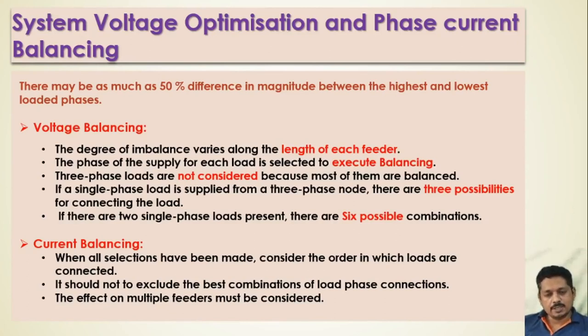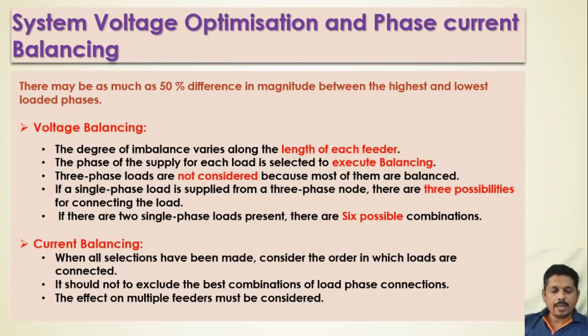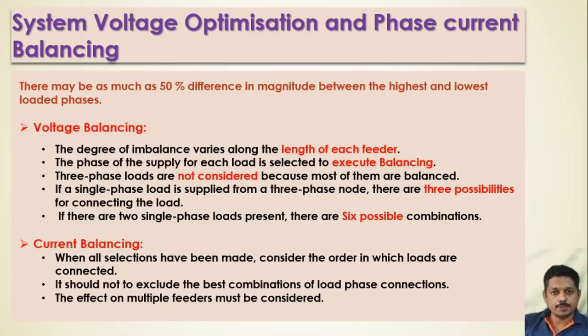If we have one single-phase load, we have three options to connect it: R, Y, or B phase. We select the appropriate phase based on load demand and phase availability. If we have two single-phase loads, we have six different configuration options — such as RY, YB, RB, and so on — to connect the loads and achieve voltage balancing. For current balancing, we follow the same steps of appropriate phase selection and connection configuration.